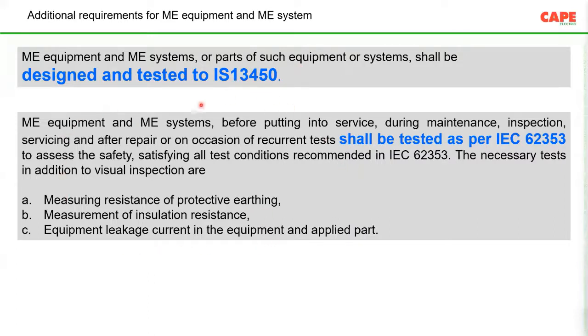Then, in the second para, you are seeing that for these systems, the medical equipment and medical equipment systems, when you put a new system into your electrical installation, or if you do a repair, maintenance or some kind of reconnection, you are also supposed to do testing as per IEC 62353. There is no equivalent Indian standard yet. So what does this particular standard say? You are supposed to test the resistance of protective earthing. That means from the equipotential bonding bar to your equipment, you have an earth wire. The resistance of that wire must be less than a certain limit, so you are supposed to measure it.